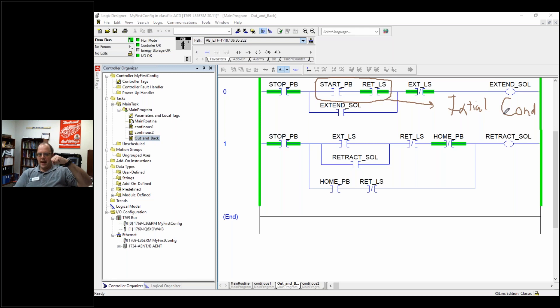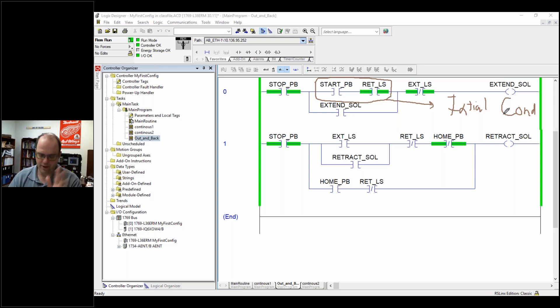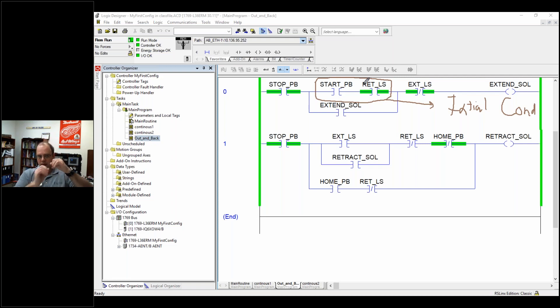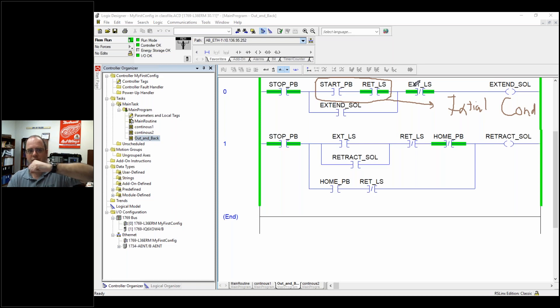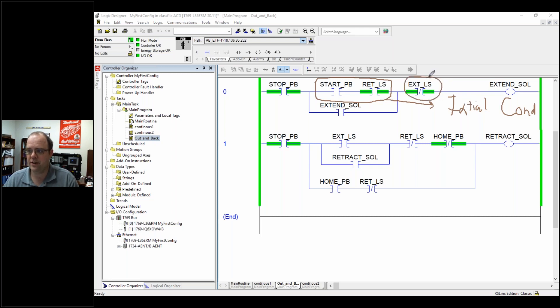So if I had a limit switch back and it had a proximity sensor that detects a part, or maybe another safety or whatever, I would put all those in there. Because then the moment I hit that push button, it's going to go off that limit switch and this will drop out to false. What cuts it off — just like our garage door — is the activation of the other limit switch. This is assuming all my limit switches are wired normally open. So this is my initial condition and everything will be in series here.